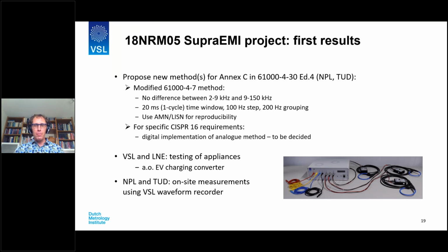Among others, NPL and TU Dresden were involved in a new proposed method that is a modification of the existing 4-7 method, such that no differences occur at 9 kHz. The 200 millisecond, or 10 cycle, time window is changed to 20 milliseconds, and frequency steps of 100 Hz are made.